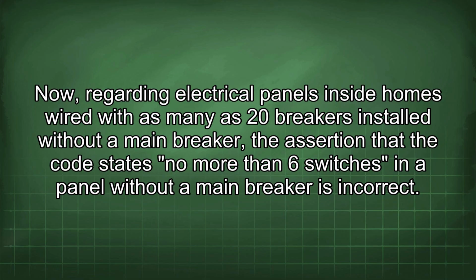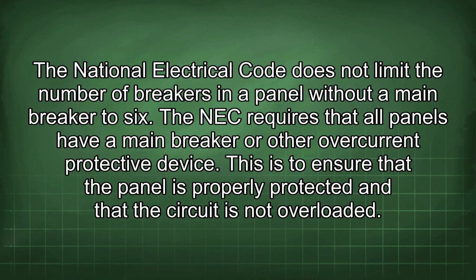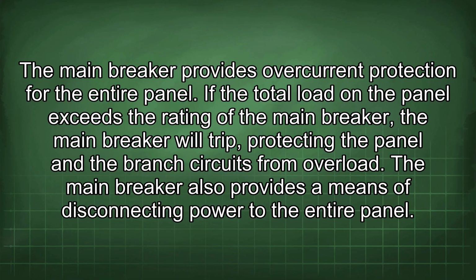Now, regarding electrical panels inside homes wired with as many as 20 breakers installed without a main breaker, the assertion that the code states no more than 6 switches in a panel without a main breaker is incorrect. The National Electrical Code does not limit the number of breakers in a panel without a main breaker to 6. The NEC requires that all panels have a main breaker or other overcurrent protective device. This is to ensure that the panel is properly protected and that the circuit is not overloaded. The main breaker provides overcurrent protection for the entire panel. If the total load on the panel exceeds the rating, the main breaker will trip, protecting the panel and the branch circuits from overload.